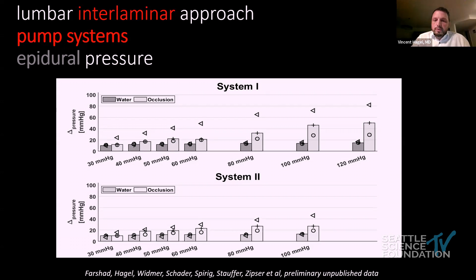Now this is the interlaminar approach, still the same setting. We're using two different pump systems. We're looking at the epidural pressure, and it's pretty much analogous to the transforaminal approach. When we occlude the working channel with the non-spine certified pump, we obviously do get high epidural pressures of above 40 millimeter mercury. Nevertheless, this does not really parallel increase the intradural pressure the same way. And if we look at the spine certified pump, system two, then even at the maximum setting of 100 millimeter mercury, if we occlude the working channel, we just barely get above 20 millimeter mercury epidural pressure.